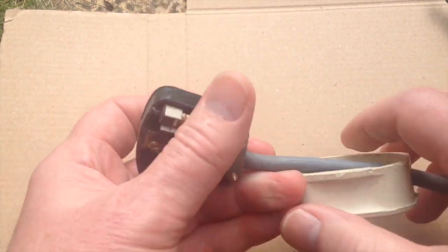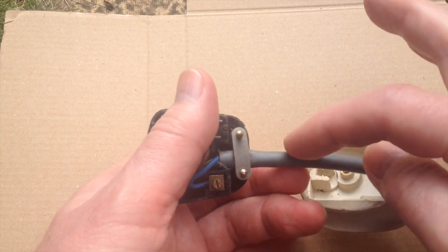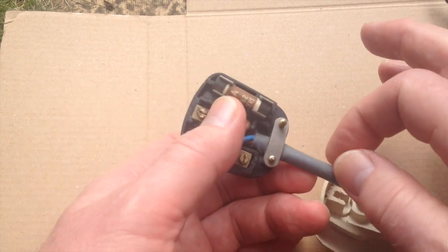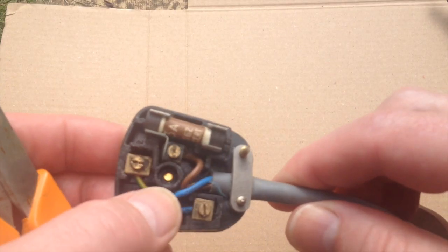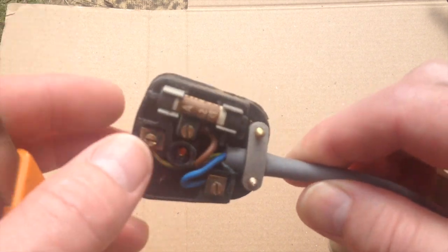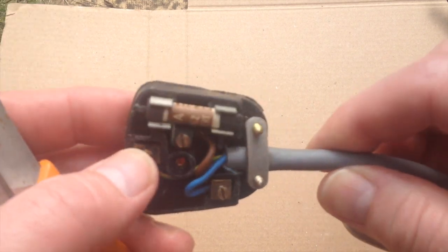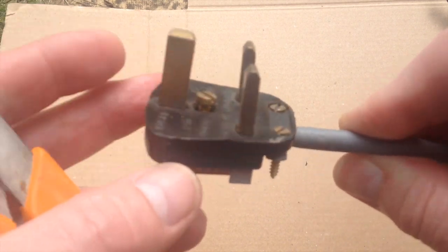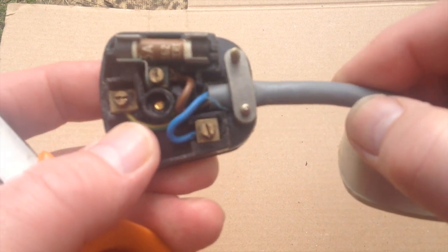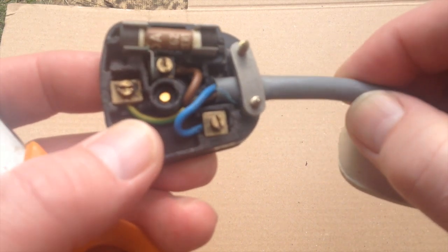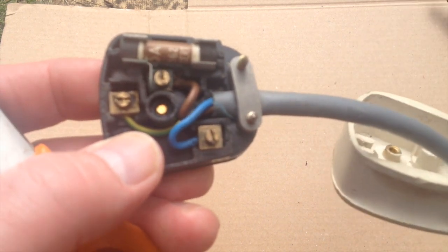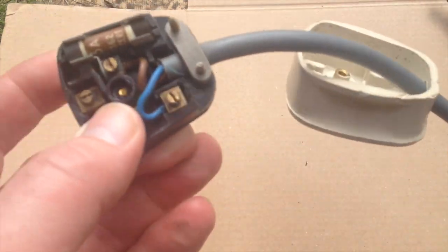So what you want to do is come back a couple of centimeters from the plug and cut the cable off. Don't under any circumstances just remove this plug and then use this same piece of wire to put another plug in, because the corrosion increases the resistance and resistance increases the temperature, so this can overheat, which is why you need to cut it back so that you've got some clean copper.